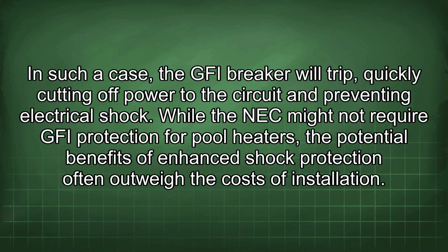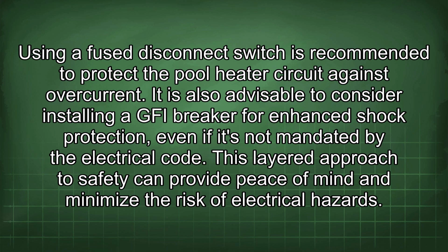While the NEC might not require GFI protection for pool heaters, the potential benefits of enhanced shock protection often outweigh the costs of installation. Using a fused disconnect switch is recommended to protect the pool heater circuit against overcurrent. It is also advisable to consider installing a GFI breaker for enhanced shock protection, even if it's not mandated by the electrical code. This layered approach to safety can provide peace of mind and minimize the risk of electrical hazards.